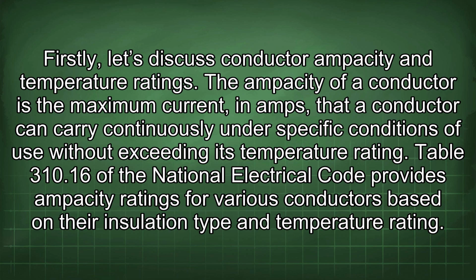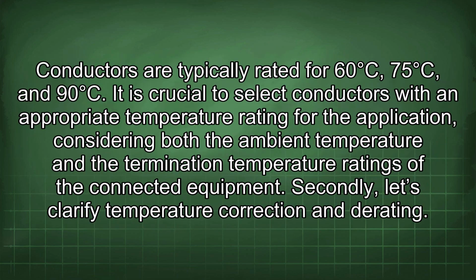Table 310.16 of the National Electrical Code provides ampacity ratings for various conductors based on their insulation type and temperature rating. Conductors are typically rated for 60 degrees C, 75 degrees C, and 90 degrees C. It is crucial to select conductors with an appropriate temperature rating for the application, considering both the ambient temperature and the termination temperature ratings of the connected equipment.